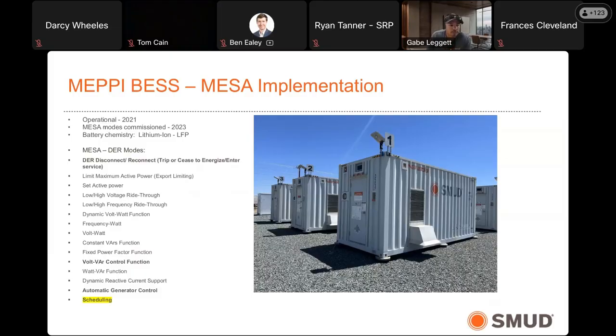Over here on the left, I have a list of some of the MESA modes that we implemented. Primarily, what we're using it for is just scheduling, so it charges during the day and discharges at night when prices are expensive. Scheduling function is very important for us, as well as when we start to move the system into market participation potentially - we're going to use the automatic generator control, taking a signal every 4 seconds and changing its active power target to meet a distributed operating target, a signal from CAISO or from a power system operator.